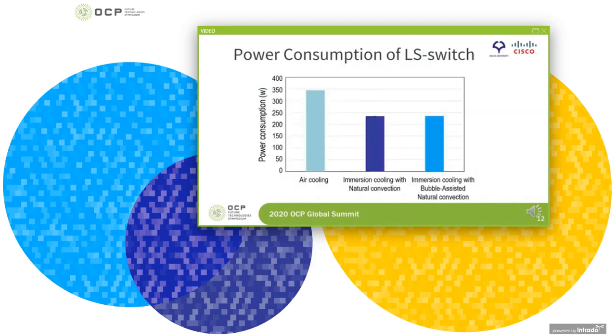How much savings are we talking about here? Well, in terms of the power consumption of the leaf spine switch itself, compared to that when air cooling is applied, natural convection immersion and also bubble-assisted natural convection reduced it by around 30%, simply due to the removal of all the fans in order to apply immersion.